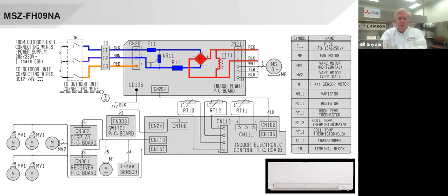that type of unit. So it's an indoor unit, but even the indoor units have boards is what I wanted to show you. This is the most complicated one. So that's what I'm going to show you. Normally the wiring diagrams have what all the symbols mean on here. Like MF means fan motor. But we're bringing in the S1 and S2 from the outdoor unit or from the branch box in here. There's a fuse. This is the NR over here stands for varistor. That can blow. If that blows, you replace the board. The fuse blows. Sometimes the fuses are soldered on and sometimes they're replaceable. Depends on the board. But the F11 would indicate a fuse.